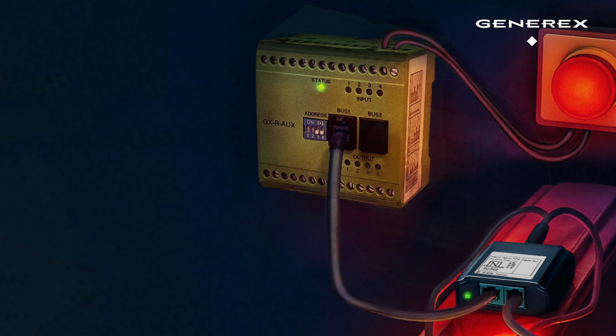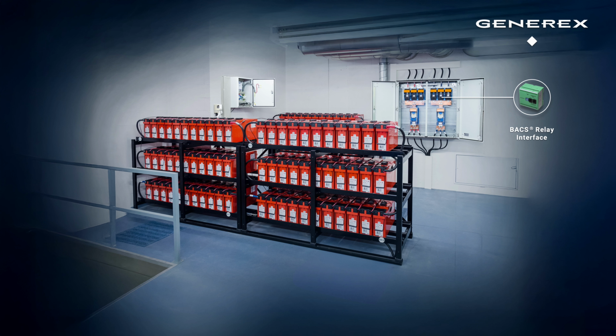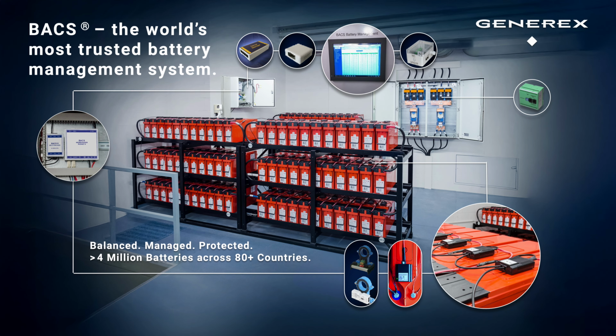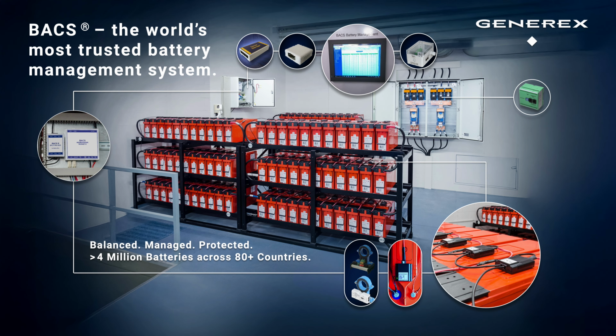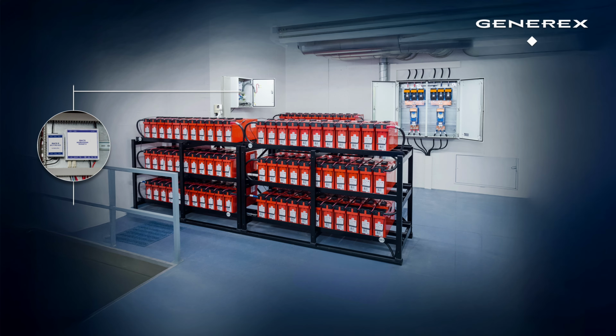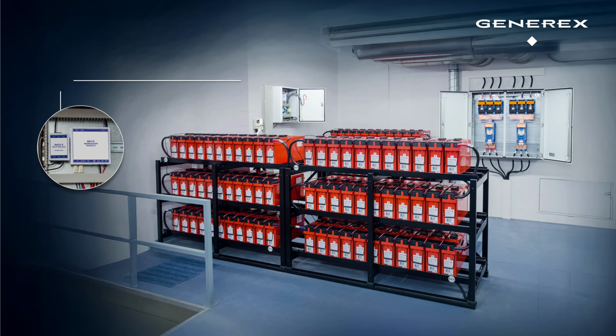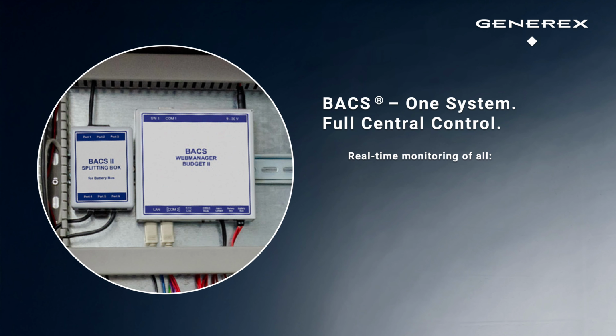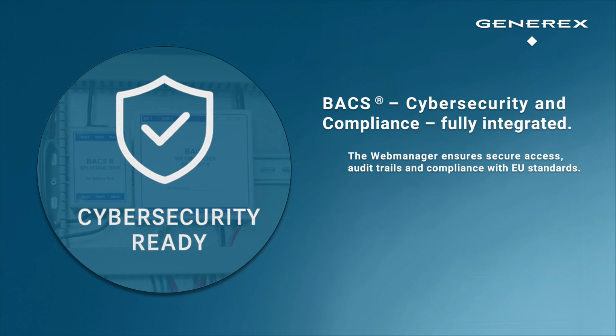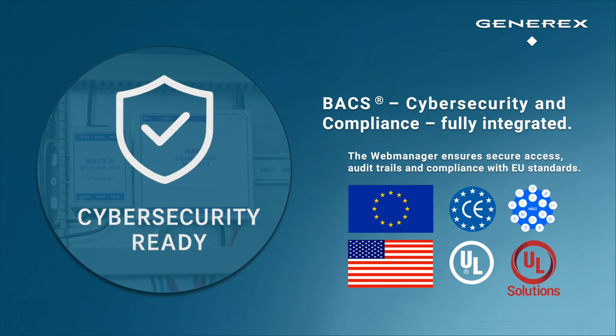BACS is the only system in the world that can physically disconnect itself from a faulty battery to prevent fire. With fuses securely welded and sleeved, BACS stands as the safest BMS on the market. In the background, you can see a BACS CC cabinet with the heart of the BACS system, the BACS Web Manager. The BACS Web Manager is a microcomputer manufactured 100% by GENEREX, also avoiding Chinese components, and is subject to constant cybersecurity checks to ensure 100% network security.